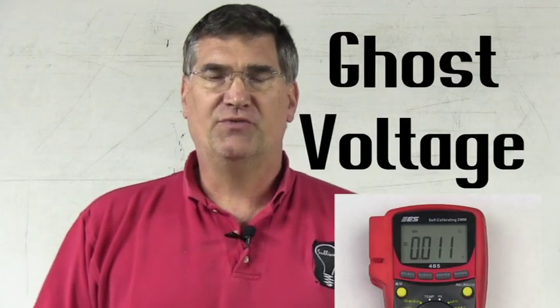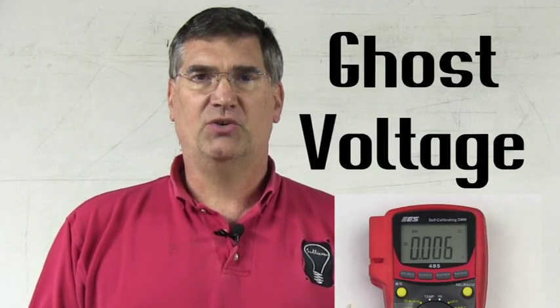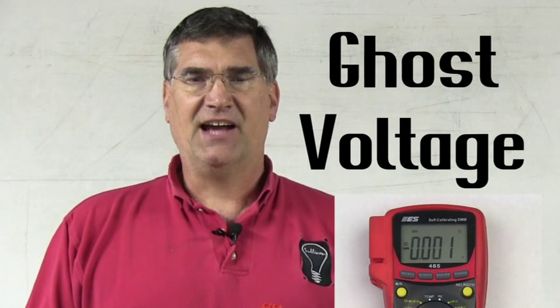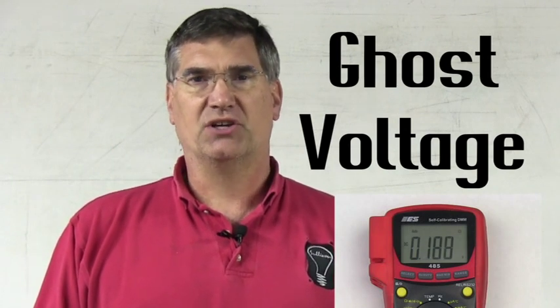First of all, there are a couple of different readings that you may not be familiar with. The first one is called ghost voltage. Ghost voltage is when the meter fluctuates and jumps around and it actually looks like it's broken or out of calibration, but it's not. Ghost voltage is an indication of an open circuit. So when you see it, you don't worry about what may or may not be wrong with the circuit or what may or may not be broken on the meter. You simply say, I have an open.